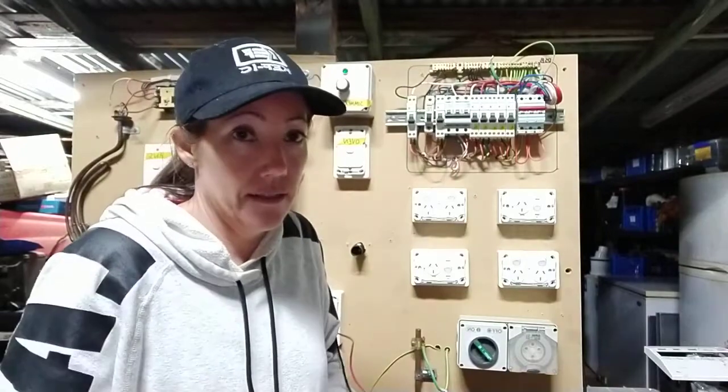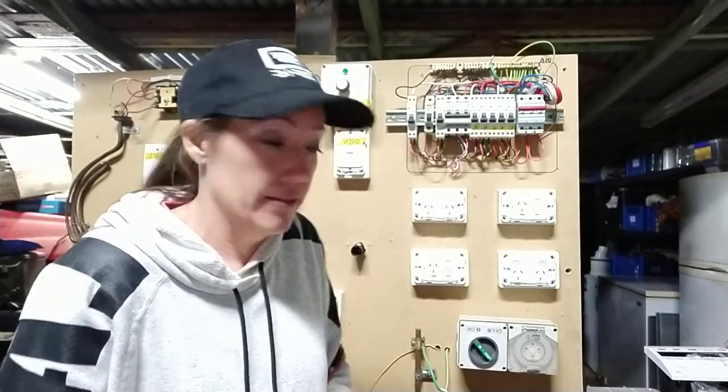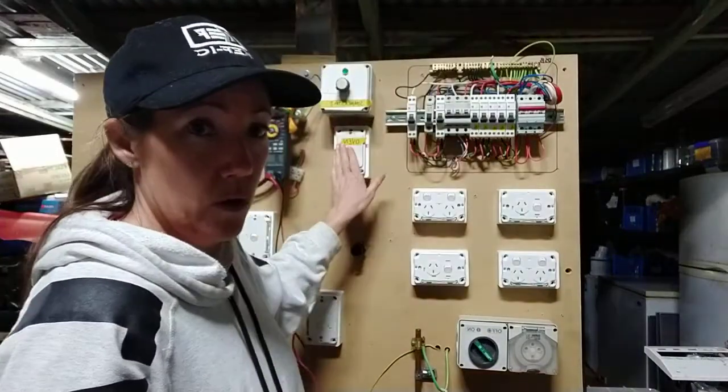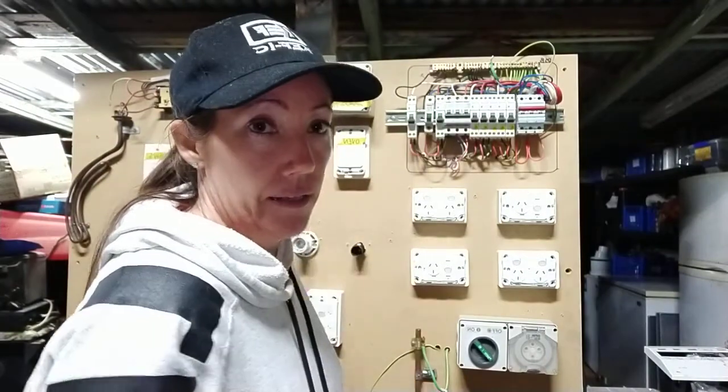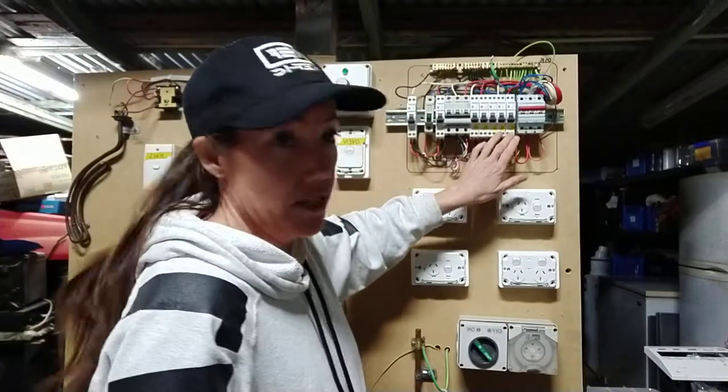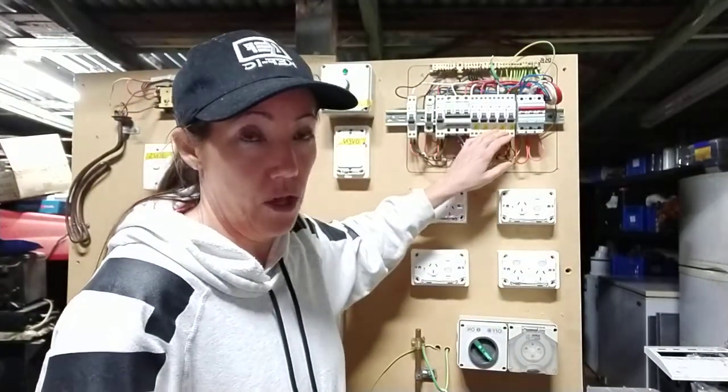First things first, make sure all your MCBs are off and turn your switches — you can toggle them on and off. That's going to help you with the test. If you have an RCD, you can test straight from active to earth on the load side of your RCD.